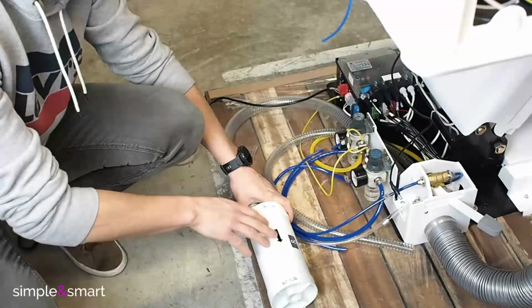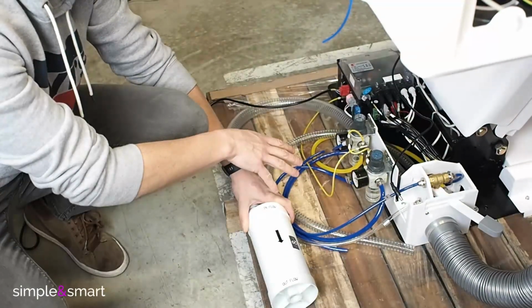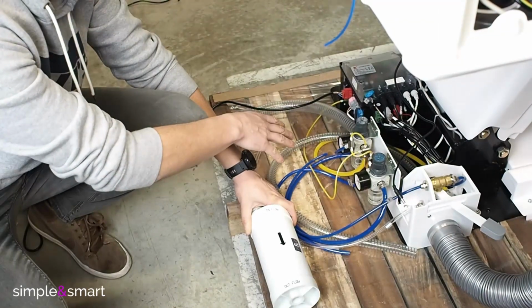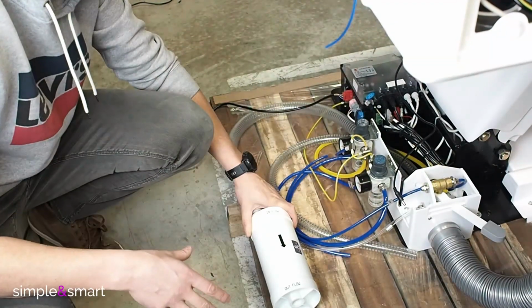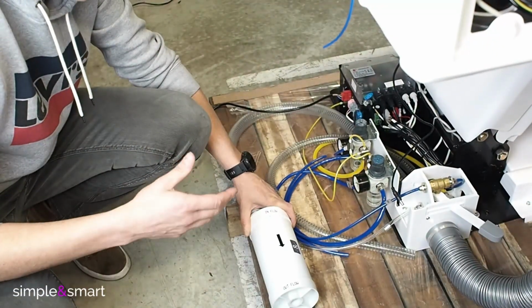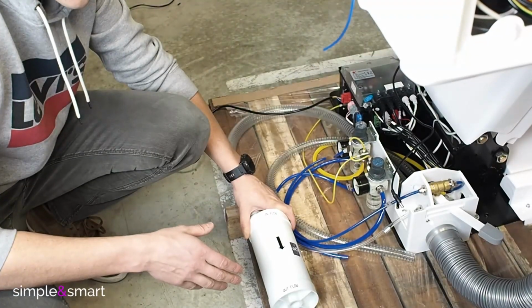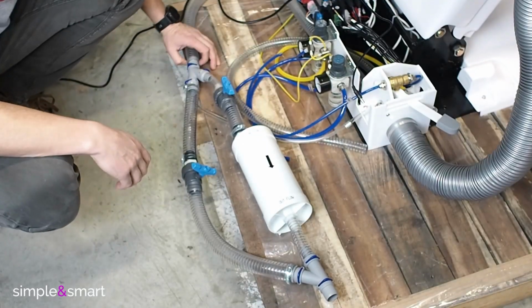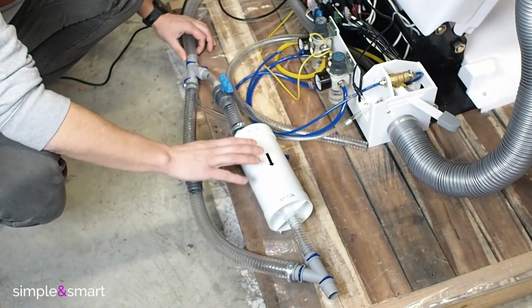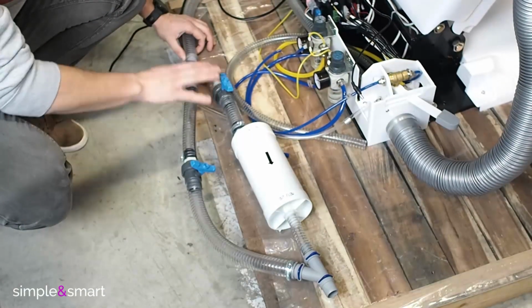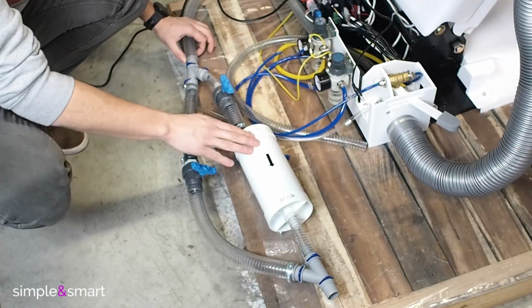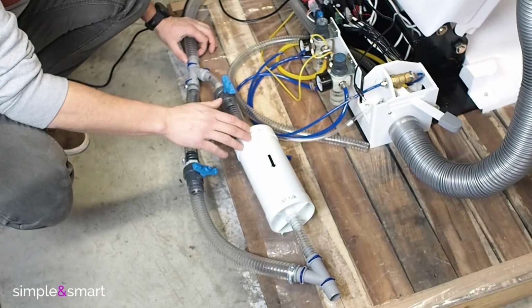This solution is fine when you can apply the filter inside the dental chair, so at the chair base if you have space, or in the machinery room when you have a wet suction motor or a liquid suction motor. The second solution is to apply a bypass. So this system permits to use the filter only when you need to use it.